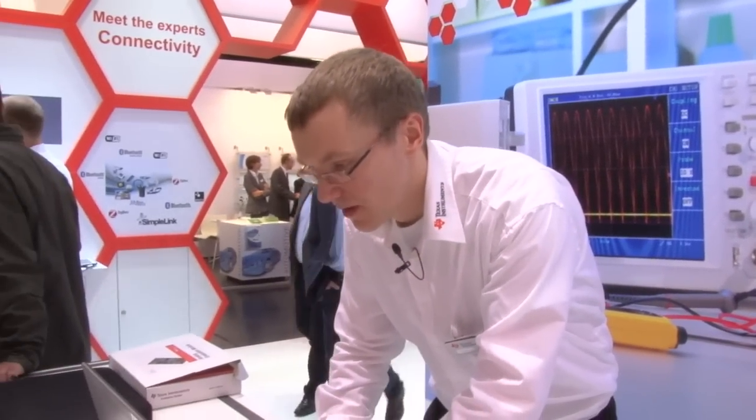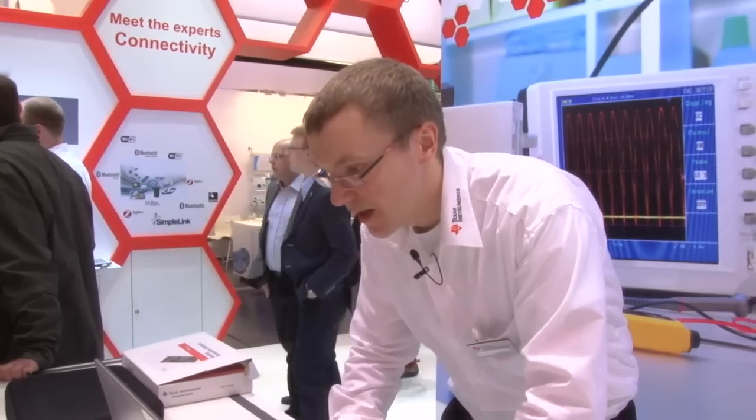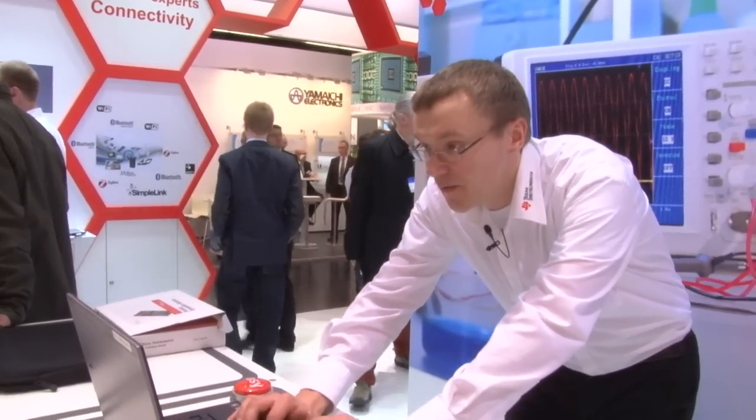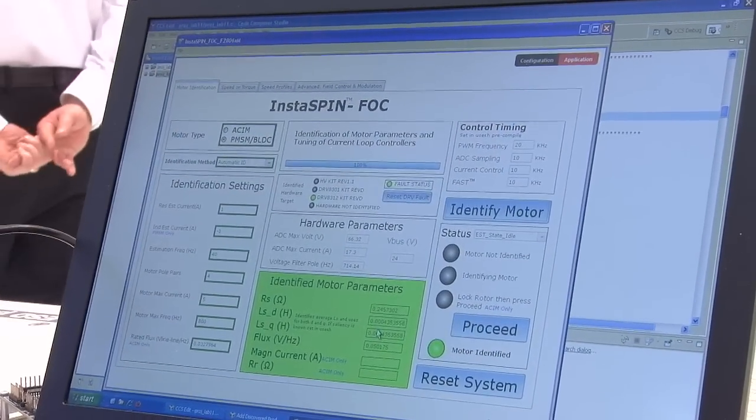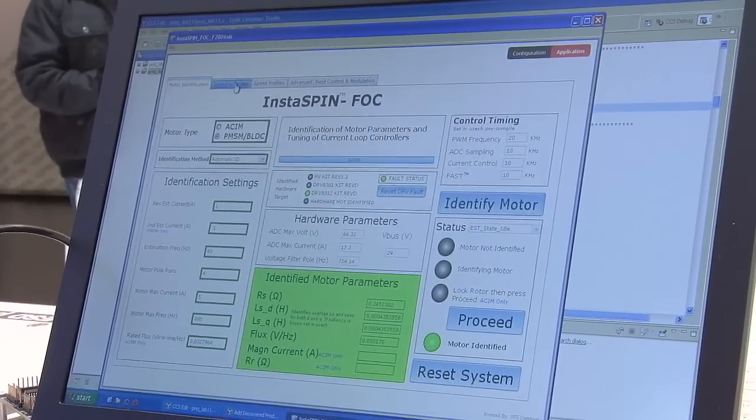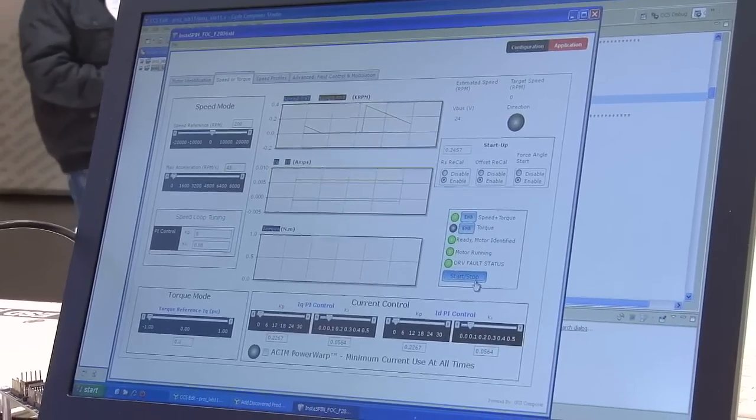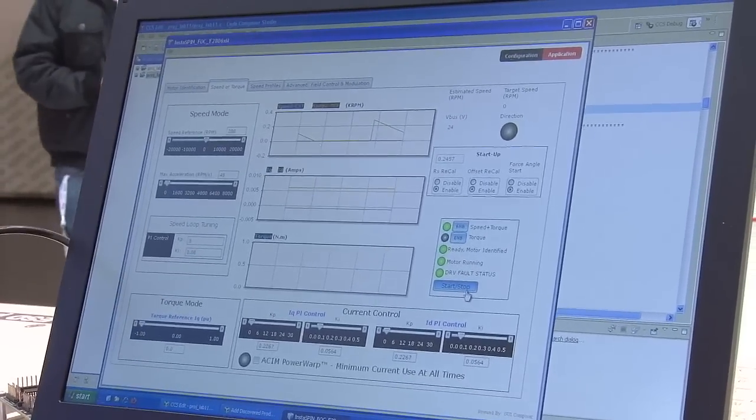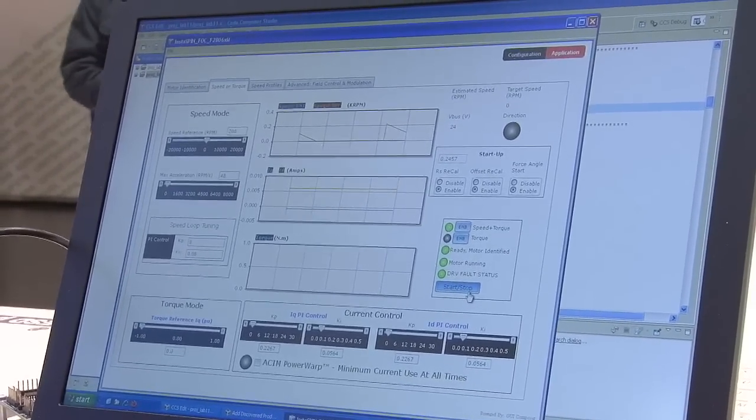So now we see that the identification is done. You see that the motor is identified and now you have the option of going into the speed and torque mode. So here you see that we do a cascaded control with a speed controller first and then a torque controller and then we generate the magnetic field that we need.